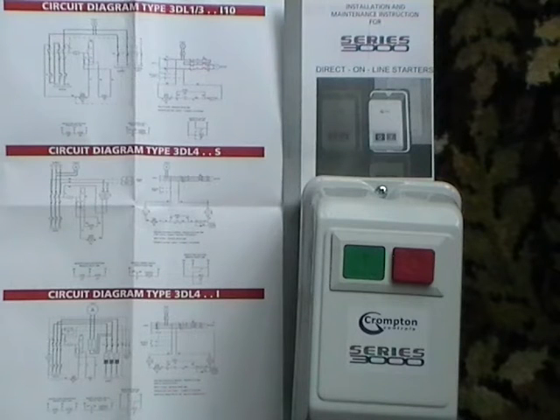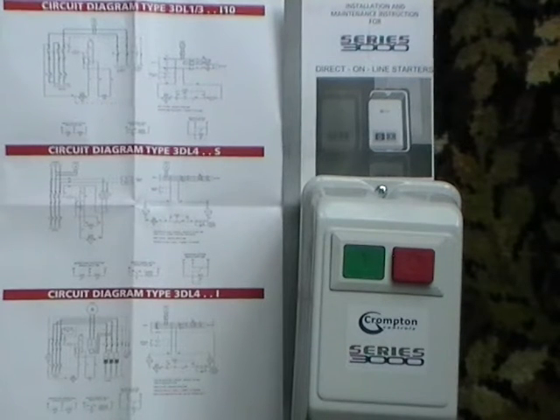In this video, I'm going to explore this particular starter because I've not wired it up internally as they are designed, and I've done that because I'm not starting a motor, I'm protecting a generator which has its own built-in limitations and doesn't need quite the same protection as a motor would when connected to a main supply which could potentially provide very large currents. My generator cannot do that, and so a little bit of tweaking is permitted, I think. So I shall now whip the cover off and detail what I've done internally to this starter to tweak it to make it suit my purpose rather than the purpose it was designed for.